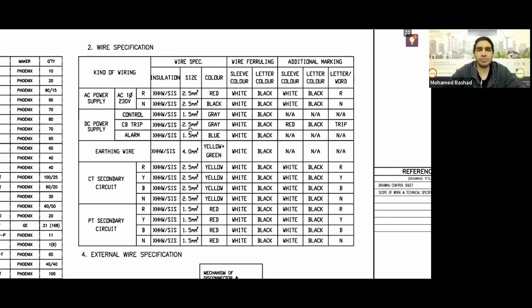This is because the circuit breaker tripping is the most important thing for me. The smaller the wire's cross-section area, the greater the voltage drop on it, and consequently the voltage reaching the tripping coil of the breaker might not be sufficient to disconnect the power. That's why it is 2.5 millimeter.